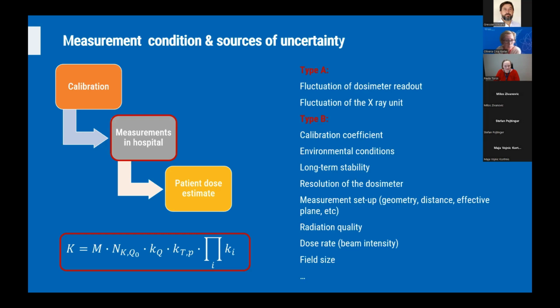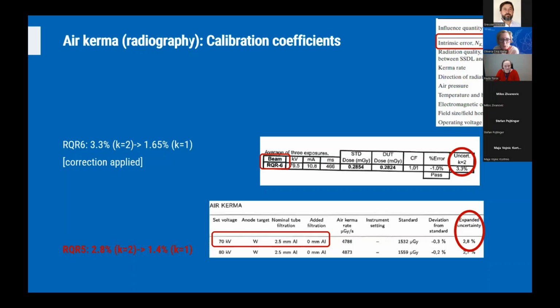If we start from the beginning, the calibration coefficient that is an essential part of the calibration certificate always comes with a certain uncertainty. Each instrument should come with a calibration uncertainty. If not, the calibration should be requested from the secondary standard dosimetry laboratory. If you look at certain elements of the calibration certificate, you will be able to identify the radiation quality, error or calibration factor, as well as the uncertainty of the calibration factor. All these parameters contribute to the overall uncertainty budget.